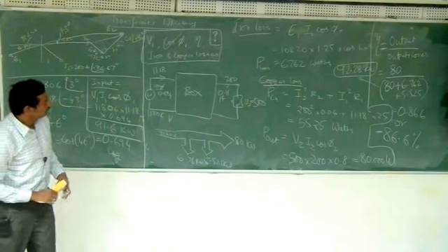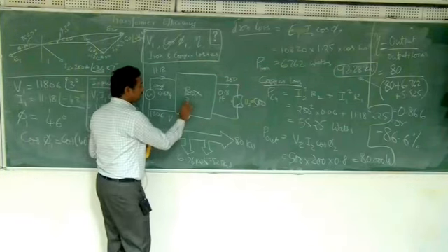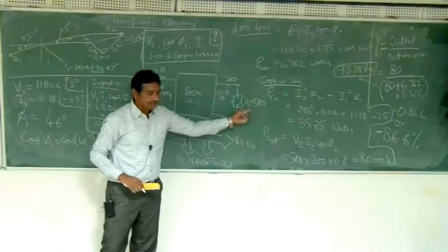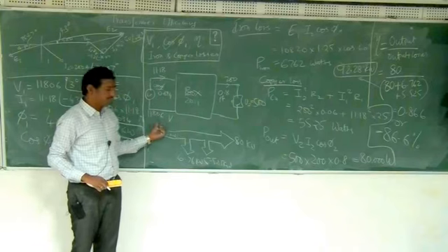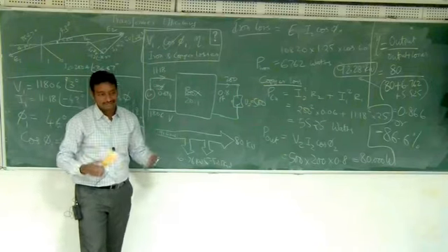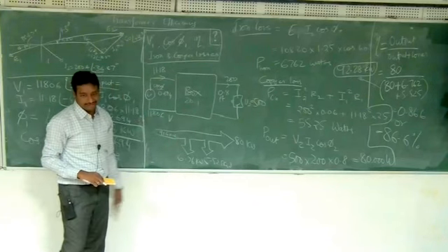Now just look at the ratio. Actually the ratio is 20:1. But if I multiply 20 into 500, I should be applying only 10,000 volts. But I am applying 11,806 volts. I am actually applying more voltage, in order to account for the voltage drops and everything.